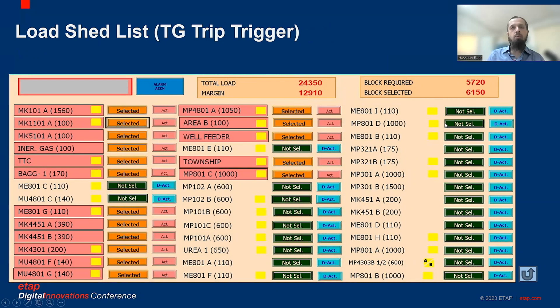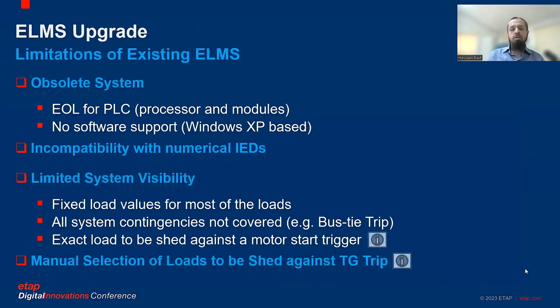The operator would go with the conservative approach, so there was some excessive load shedding each time. Again, there was a potential of misoperation of the system in case a motor load just cuts in, starts or stops, and the TG trips before the operator makes some selection or changes in this screen. So again, there was a chance of under or overload shedding. These were the limitations of the existing system.